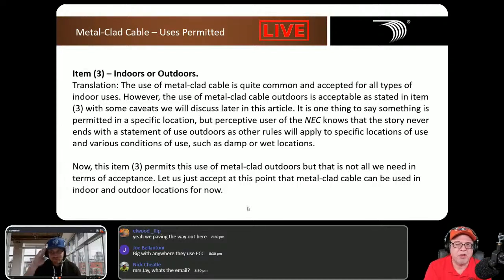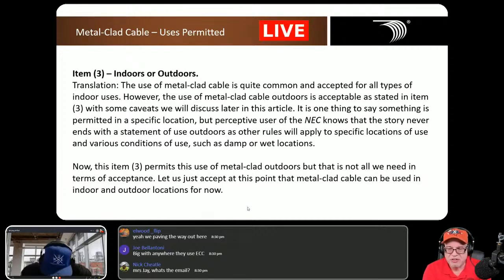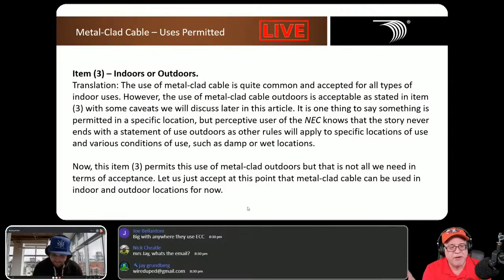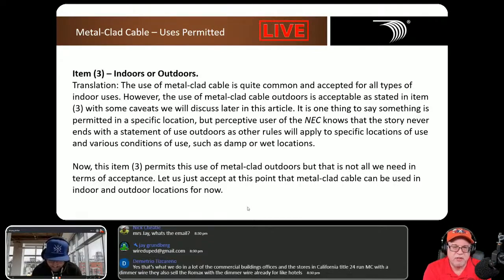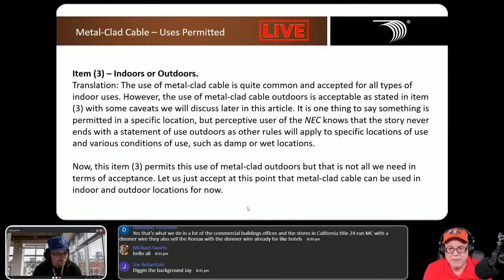Next item 3, we come to the infamous indoor and outdoor. When we hit this on the list, the interesting thing is it not only talks about specific conditions, but is also very location driven. For indoor and outdoor: use of metal-clad cable is quite common and acceptable for all types of indoor uses. However, use of metal-clad cable outdoors is acceptable as stated in item 3, with caveats we'll discuss a little later.